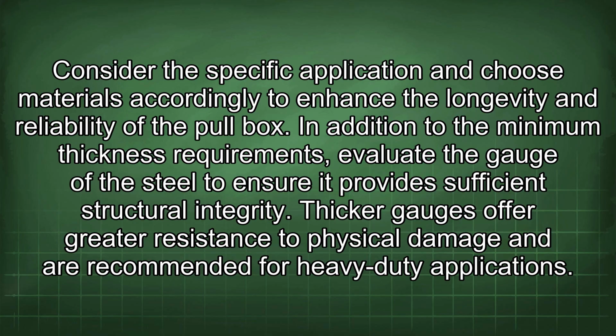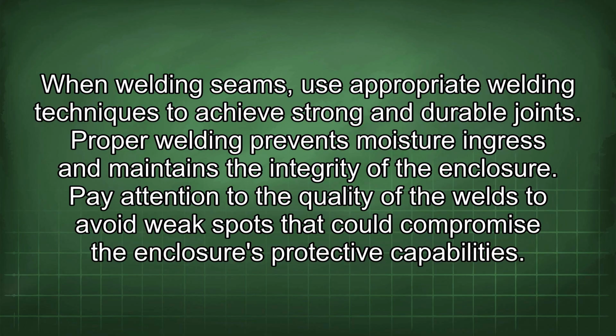In addition to the minimum thickness requirements, evaluate the gauge of the steel to ensure it provides sufficient structural integrity. Thicker gauges offer greater resistance to physical damage and are recommended for heavy-duty applications. When welding seams, use appropriate welding techniques to achieve strong and durable joints. Proper welding prevents moisture ingress and maintains the integrity of the enclosure. Pay attention to the quality of the welds to avoid weak spots that could compromise the enclosure's protective capabilities.